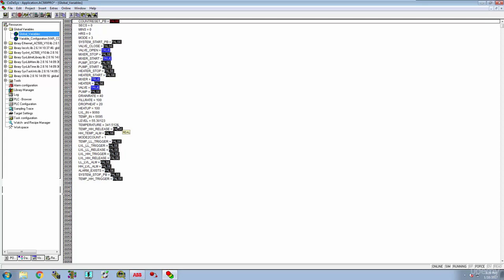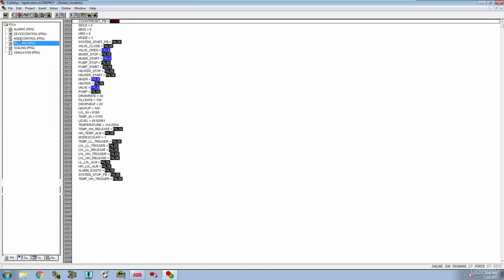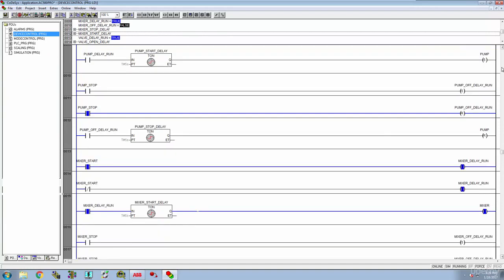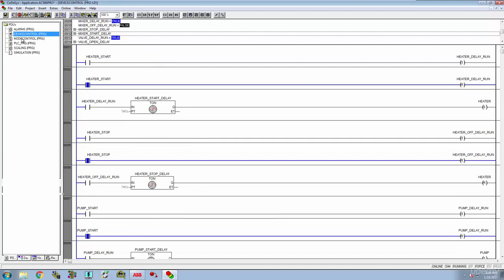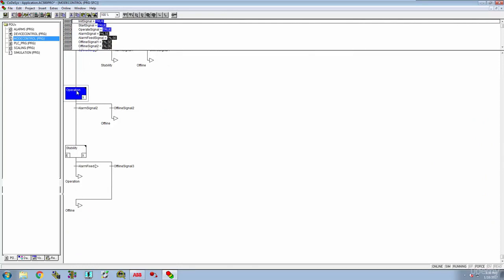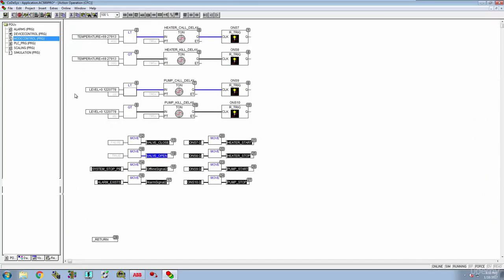Once we get a little bit lower we should see our heater coming back on. I don't remember what the set point was on that, but I know we've got a 5-second delay and I'm not seeing our heater come on. So let's go back into the logic and see what's going on. I'm going to go straight to device control — it looks like we are handling our triggers and resets just fine. Let's go into mode control and look under operation.